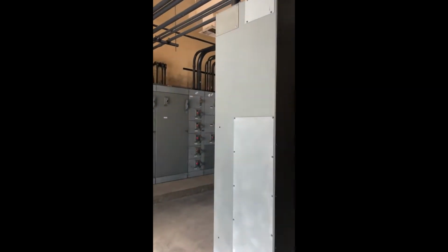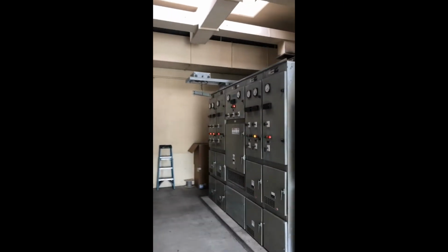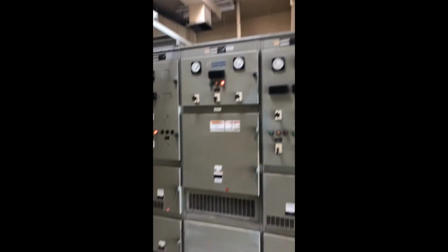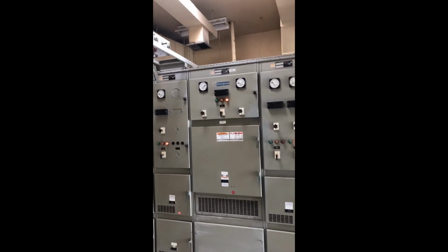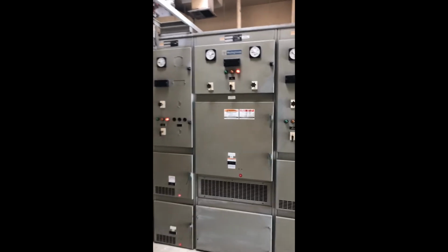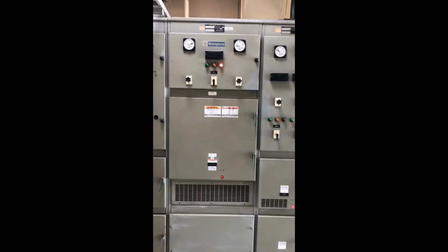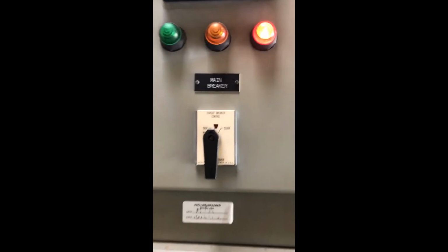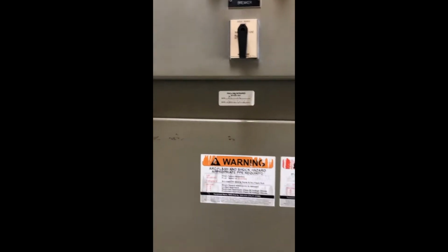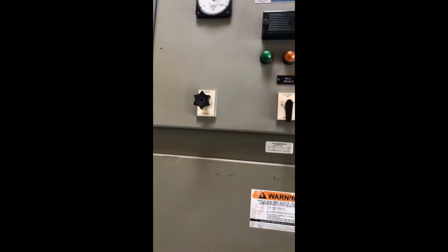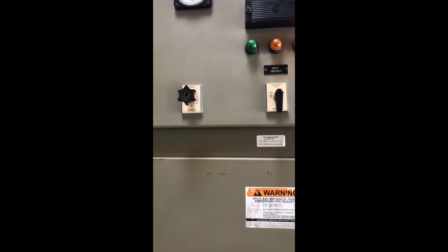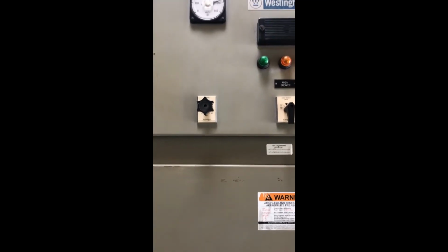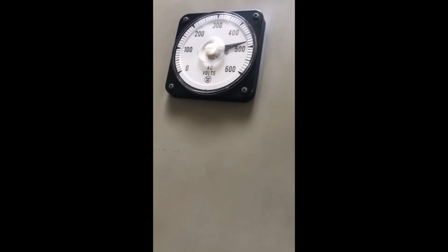So now I am directly above the maintenance shop, and this is where the power comes in. This is our distribution switchgear that we covered in the beginning of the class. In the center is the main circuit breaker. This is where you can come if there's no power at the plant. And we talked a little bit about the voltage transformers, the PTs, and they're inside this panel, and they knock down that 480 volt to a much lower voltage. I believe it's 120.